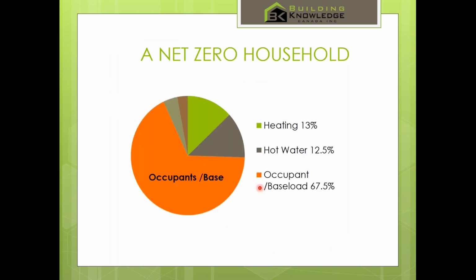Now, if you take the net zero home and take it even farther, all of a sudden that heating load is down around 13%. Hot water has dropped as well. And the big kahuna here, the big issue, is the base load. It's quite interesting to think that in most net zero homes being built right now, and many of you I see online have been intimately involved in this, 2/3 of the solar panels on your net zero home are doing just your plug loads. So it's your iPods and your stoves and your fridges and your hot tubs that are the real worry, whereas if all it meant to be net zero was just to do heating, cooling, ventilation, hot water and air conditioning, it would take about 1/3 of the panels, which is sort of interesting.